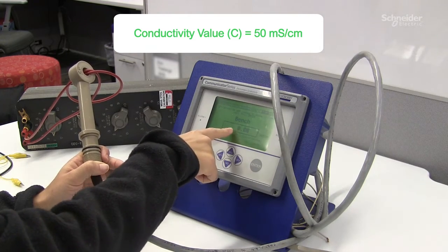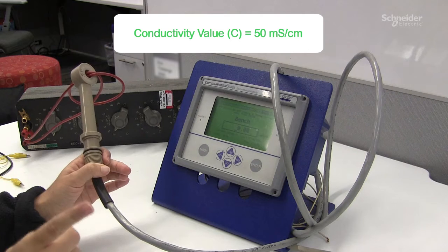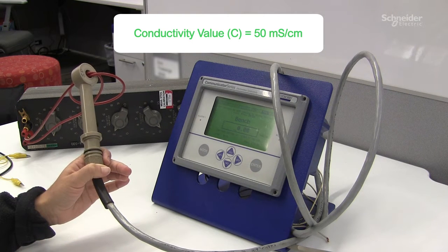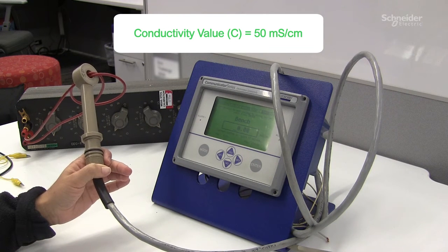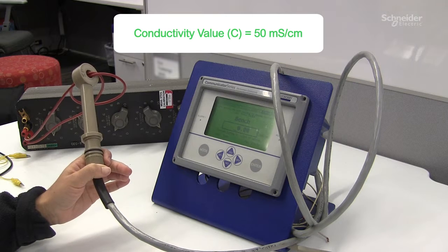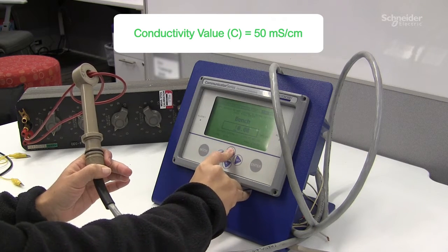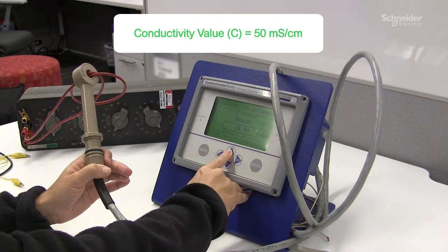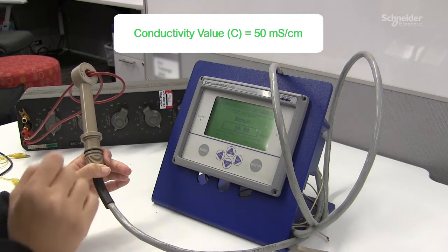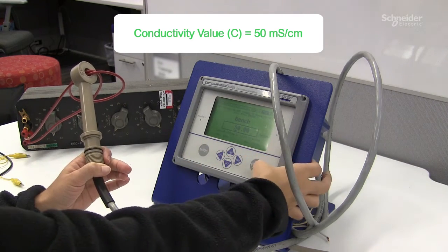Go to the first digit and enter the millisiemens that would correspond to your maximum conductivity limit. In our case it's going to be 50, five zero millisiemens per centimeter. Press enter.